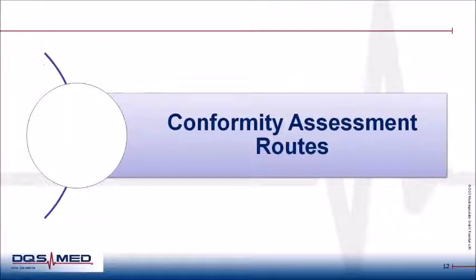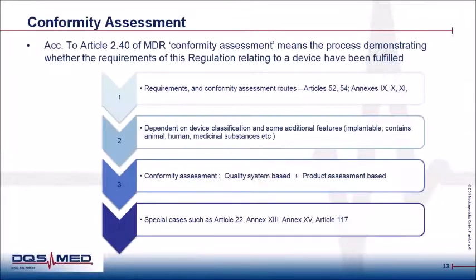Now let's move to the conformity assessment routes presented by the MDR. According to Article 2, Paragraph 40 of the MDR, conformity assessment means the process demonstrating whether the requirements of this regulation relating to the device have been fulfilled or not fulfilled. Conformity assessment in the new MDR is essentially unchanged from the current Medical Device Directive. The MDD's conformity assessment article has really been just renumbered. So Article 11 of the current MDD will be replaced by Article 52 of the new MDR.